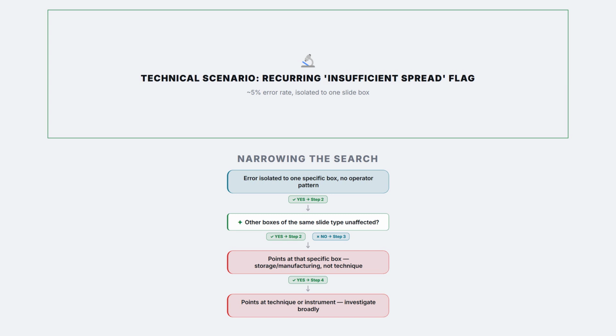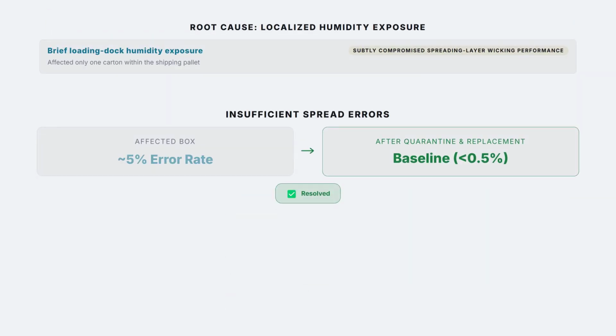Investigation traces the affected box to a shipping pallet stored briefly near a loading dock door during an unusually humid week, subtly compromising the spreading layer's wicking performance on just that carton without visibly damaging the packaging. Quarantining and replacing that specific box, while leaving the rest of the lot in service, resolved the error rate to baseline immediately. The troubleshooting discipline worth internalizing.